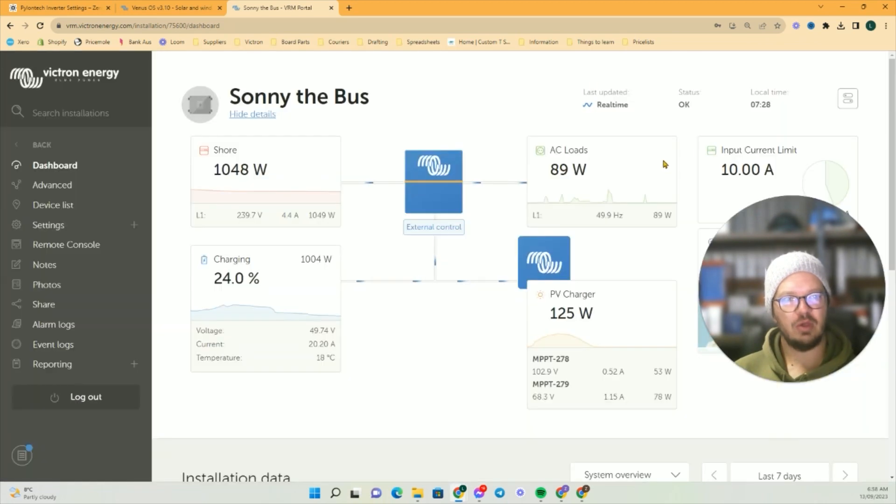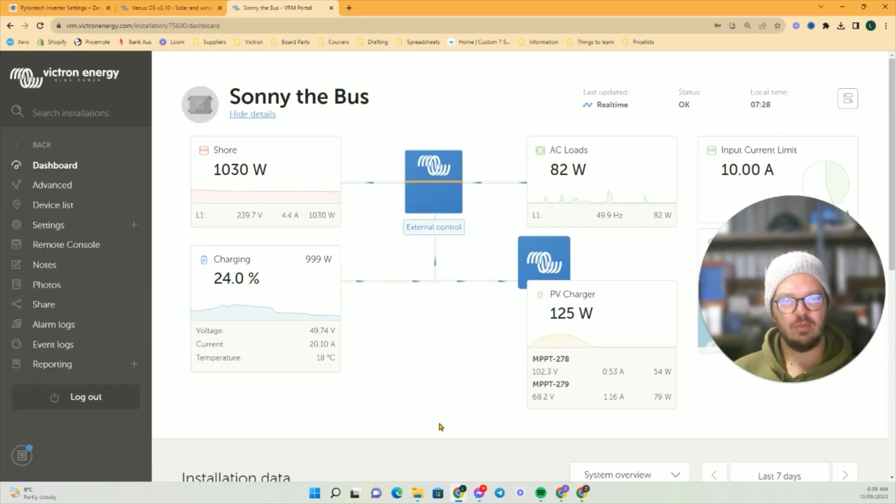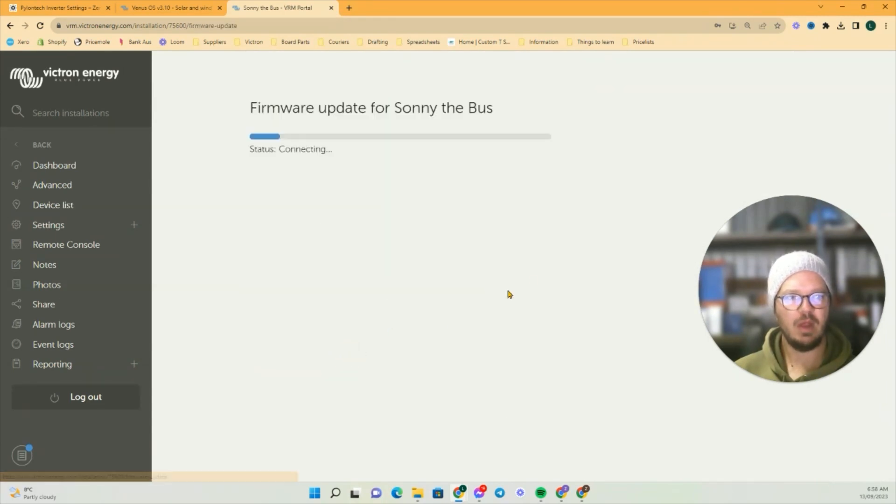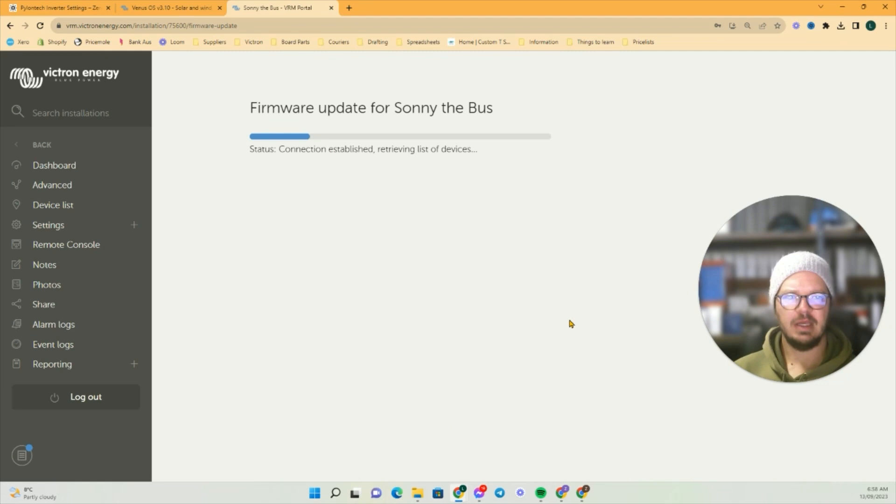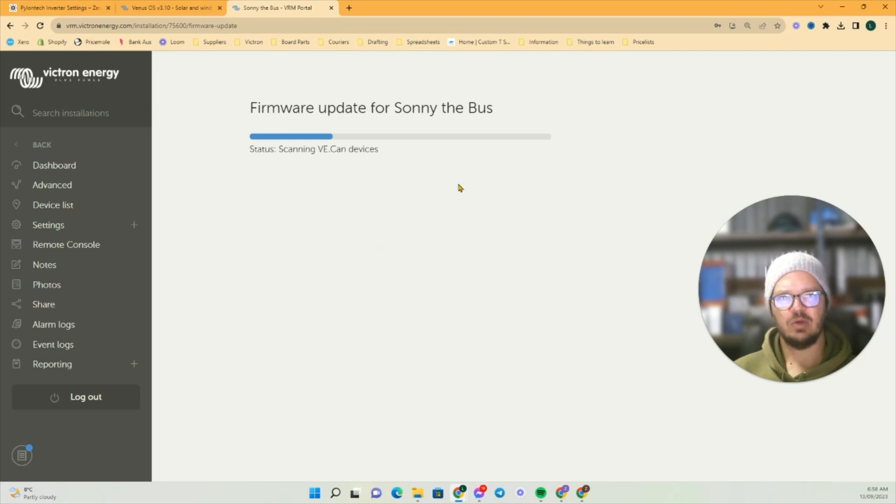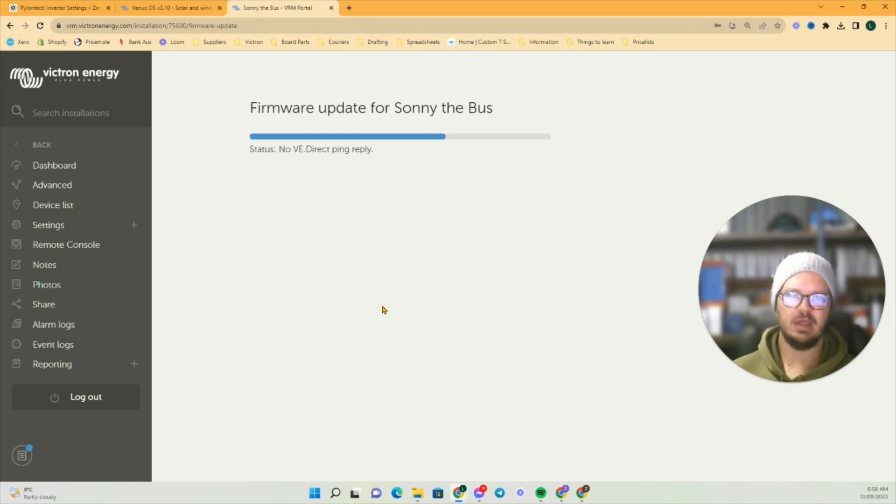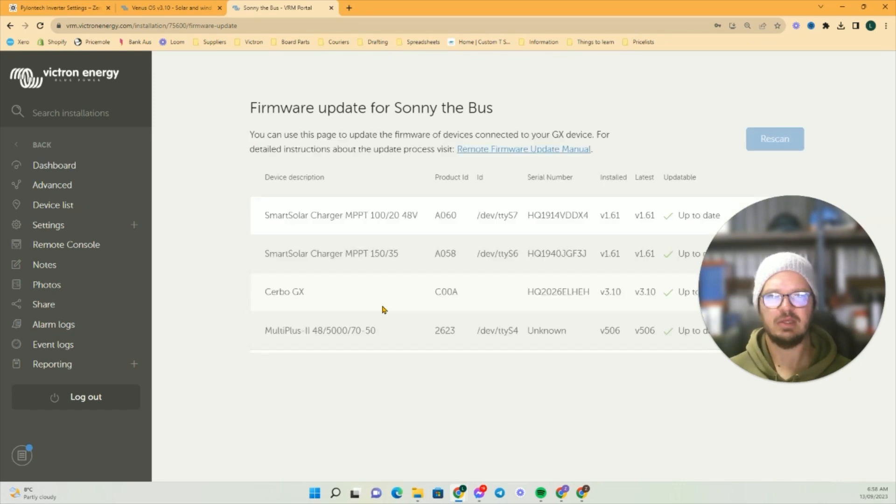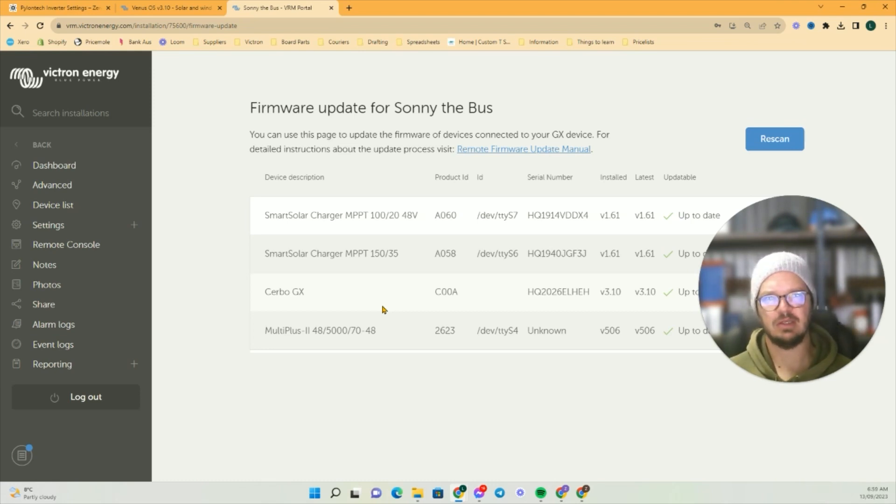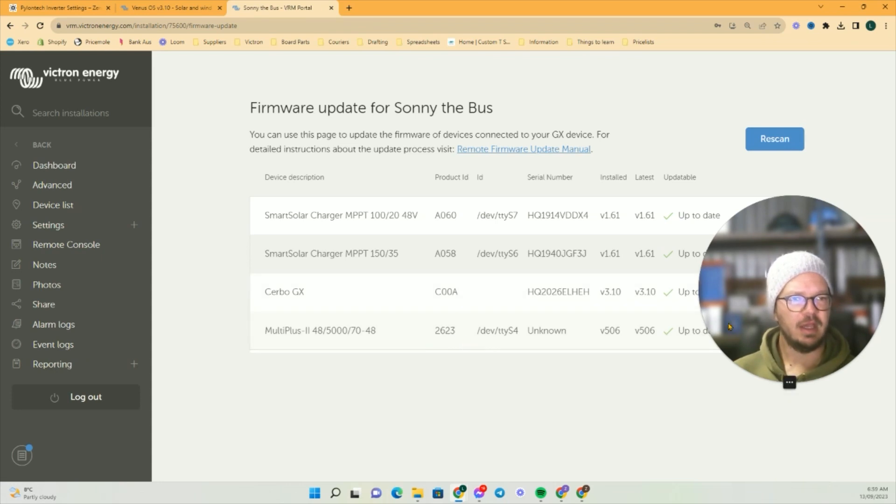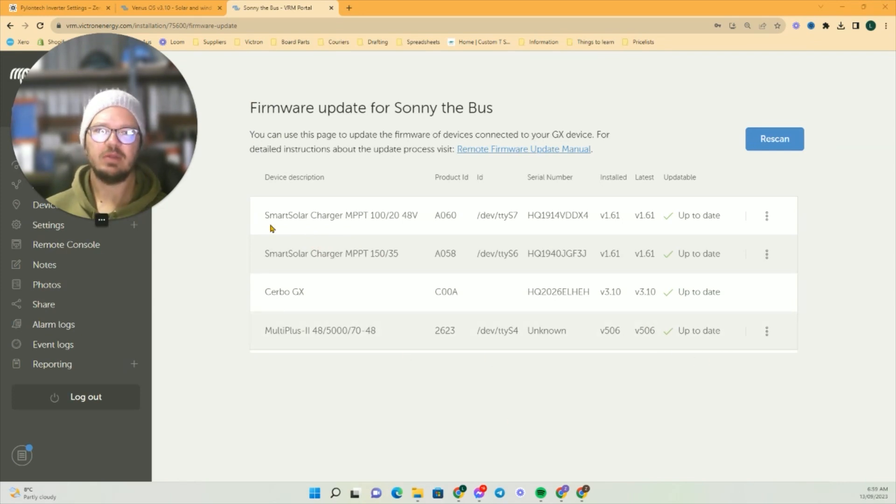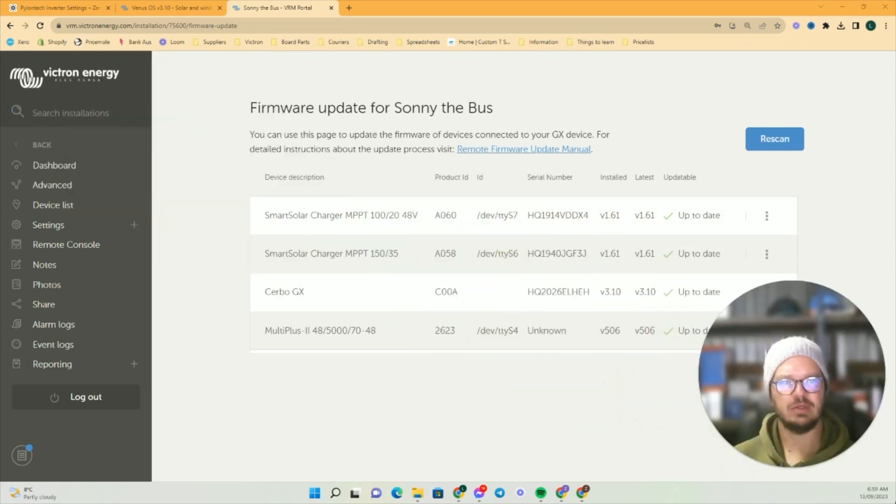Step number two: we want to go to the VRM. If you've not set up with the VRM, I can show you how to do that. Then we go to Device List, Firmware Update. There is a caution around doing the firmware updates—we don't really want it to be relying on an internet source that is powered from the inverter, because if the inverter drops out halfway through and loses its internet, it can be a hassle. So it's best to use a hotspot on your phone or plug the internet into a different service, or have it run off your DC side of things as well.